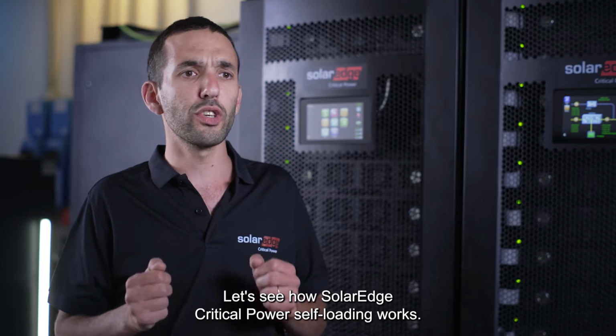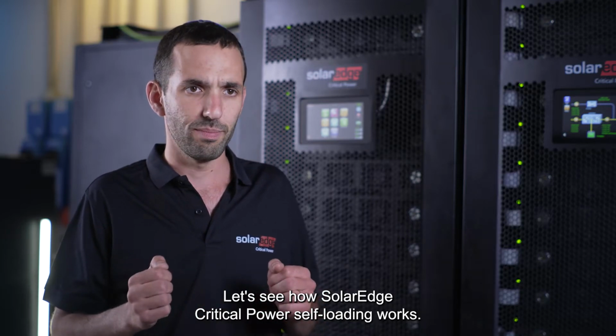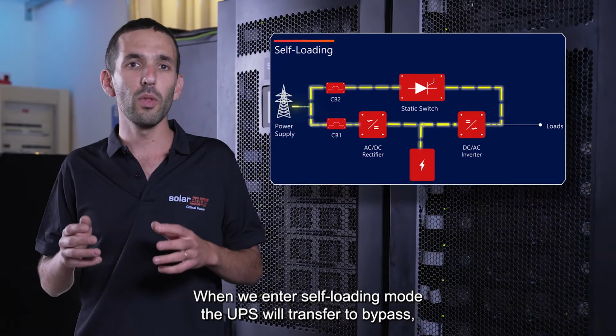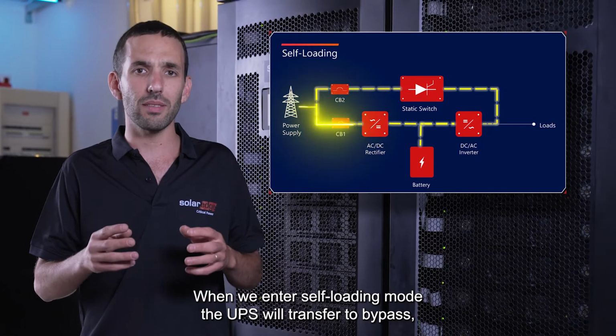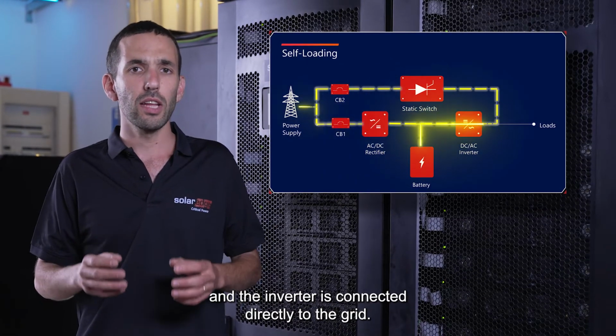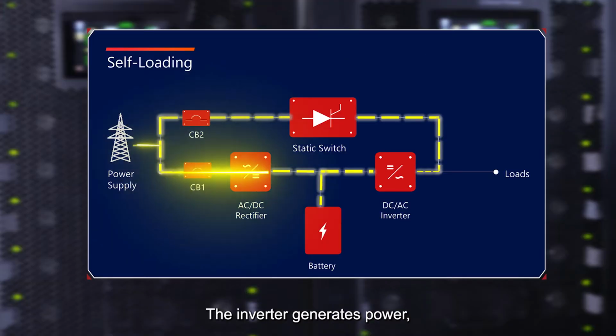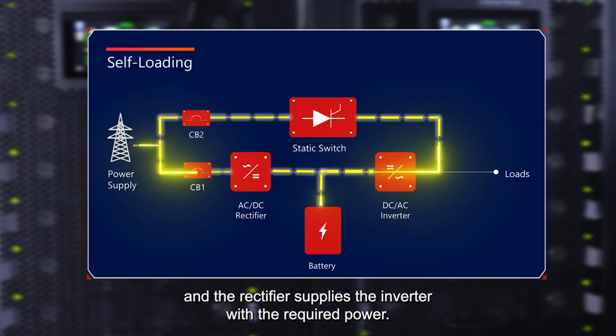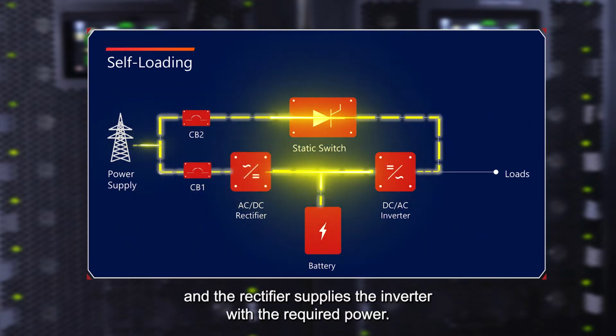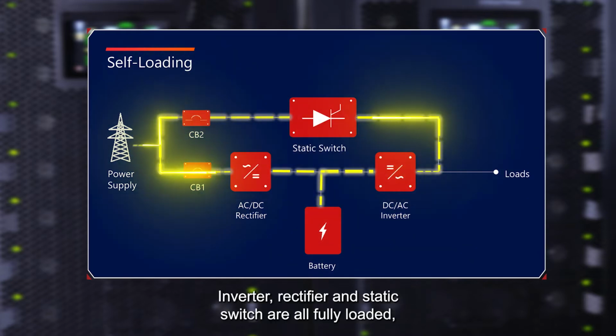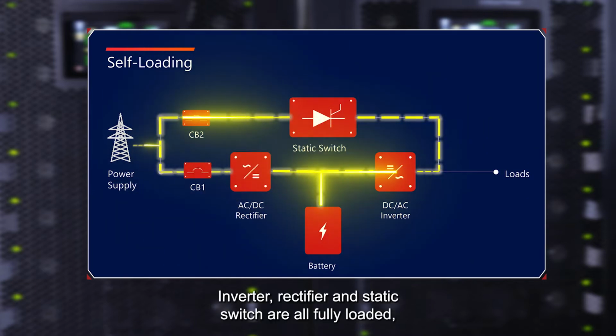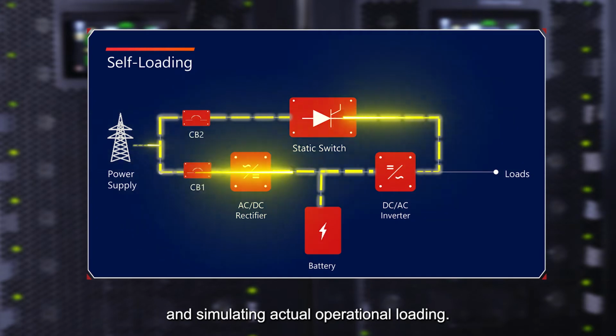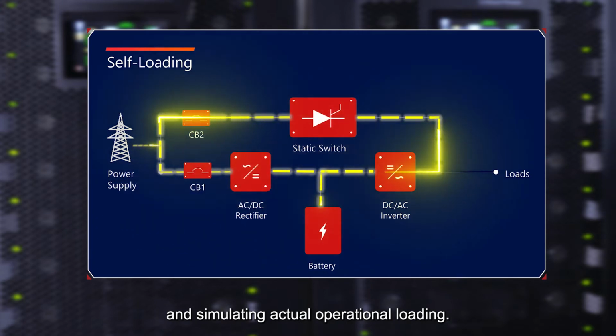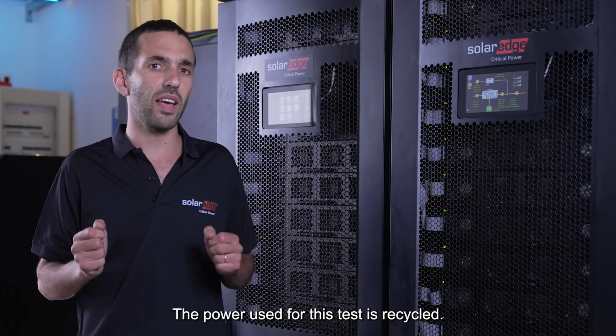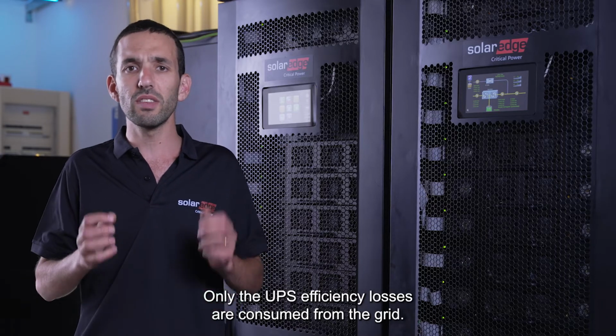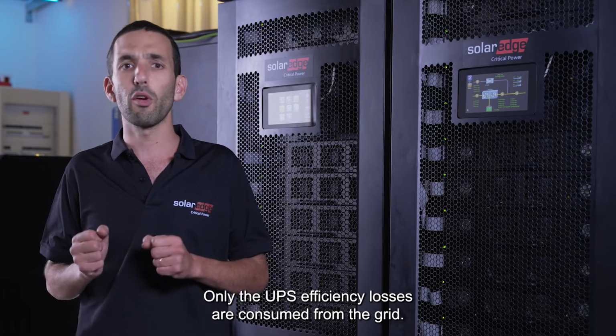Let's see how SolarEdge Critical Power self-loading works. When we enter self-loading mode, the UPS will transfer to bypass, and the inverter is connected directly to the grid. The inverter generates power, and the rectifier supplies the inverter with the required power. Inverter, rectifier, and static switch are fully loaded and simulating actual operational loading. The power used for this test is recycled. Only the UPS efficiency losses are consumed from the grid.